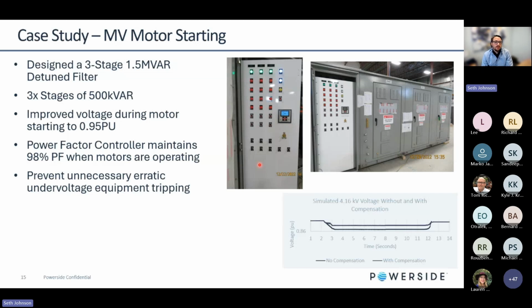And then the other thing, of course, is that you'll notice it is a detuned filter. One of the things we looked at during the power systems analysis was that there was a significant amount of harmonics during the motor starting sequence due to the soft starting application under which these motors were being operated. So the detuned filter allowed us to dampen the system so that we're not amplifying harmonic content during the motor starting event. Again, another great case study of how we use the power systems analysis program to come up with and determine a solution that the client didn't really know existed, but solved their problems and even went a step further to provide the VAR compensation under normal operating conditions.